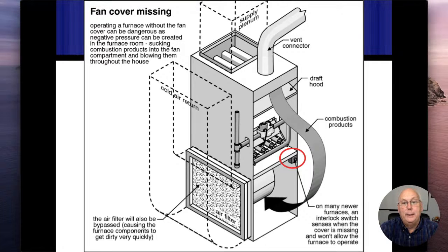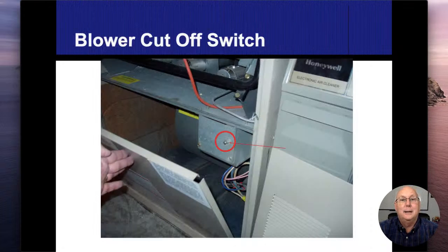Having these things operate and depressurizing a room, it does happen. It is rare. This is mostly going to be a problem on a natural draft furnace, not so much on a high efficiency or a mid efficiency furnace. But what we're talking about, and maybe the next slide will show this.